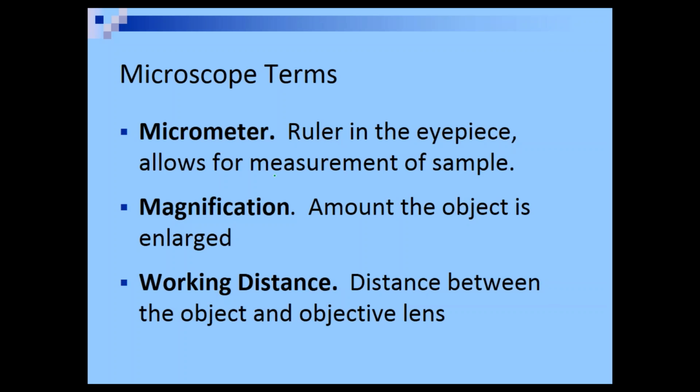The solution for this is putting the ruler in the eyepiece. It's actually a thin disc of glass that you put in the eyepiece. So you're looking through this transparent ruler, and it's always projected on top of the image of whatever you're looking at. The ruler will have different dashes in it, but those dashes won't have numbers. It'll have a conversion chart, because when you're at 10 times magnification, maybe every slot is 1 micrometer.